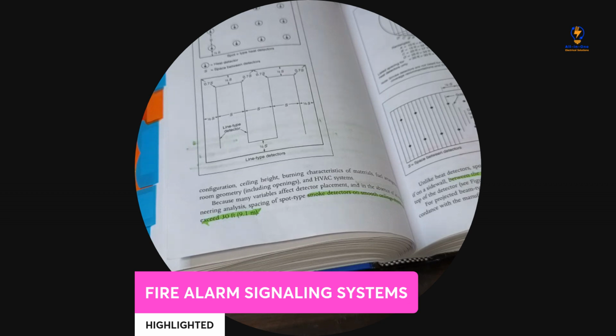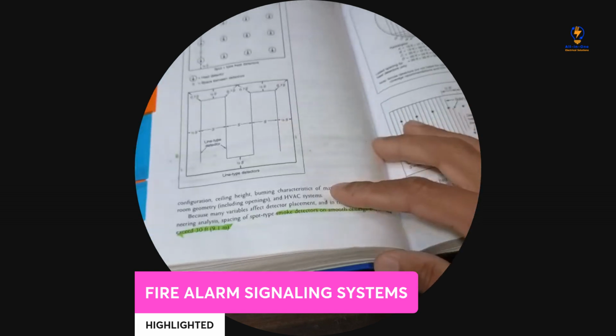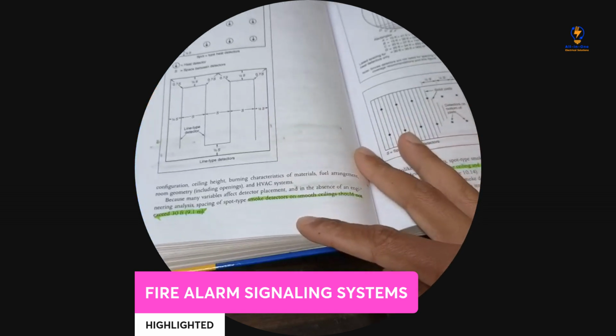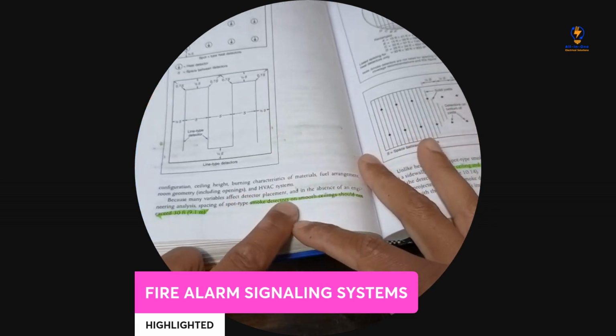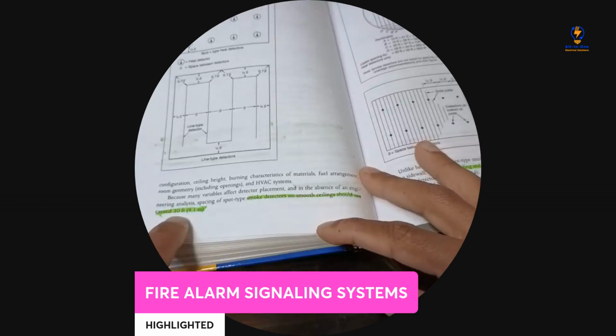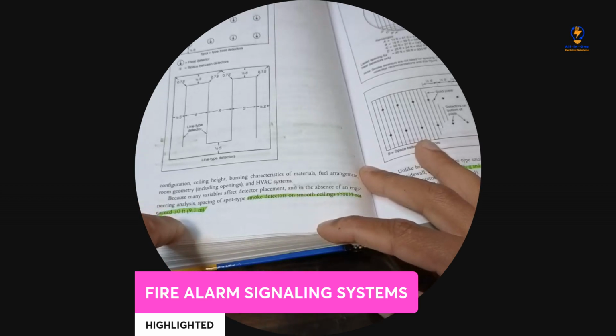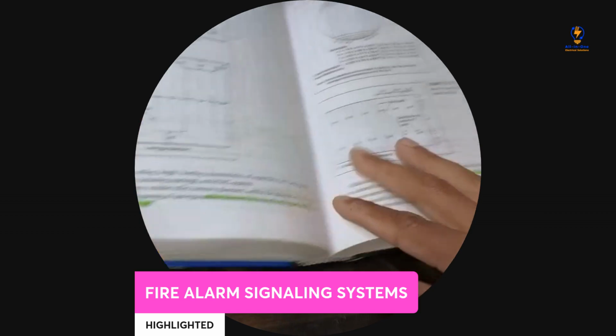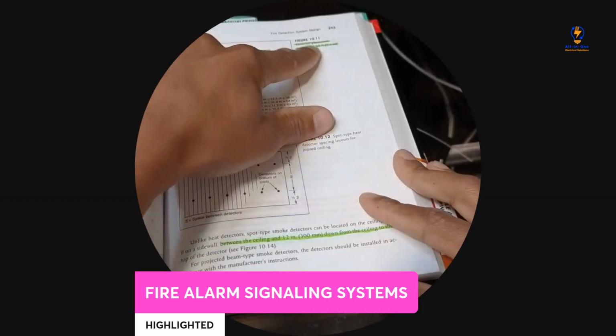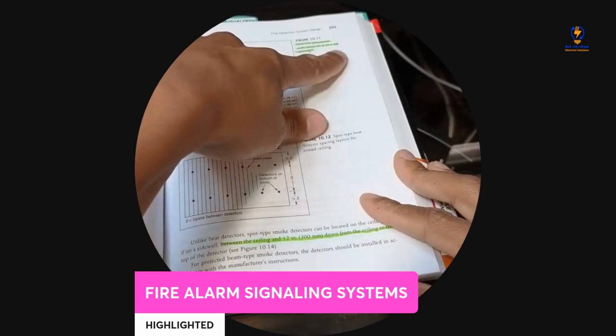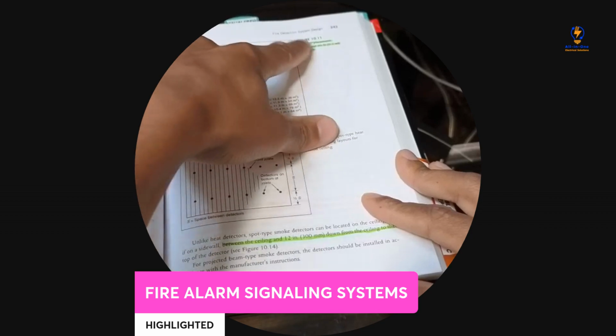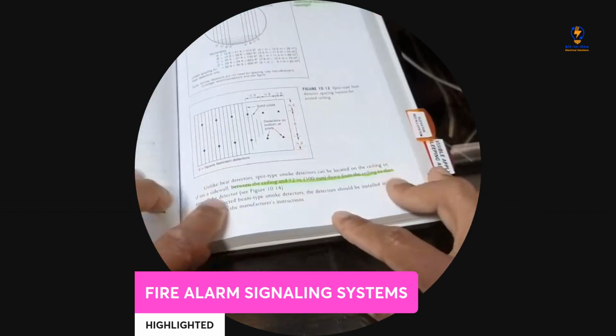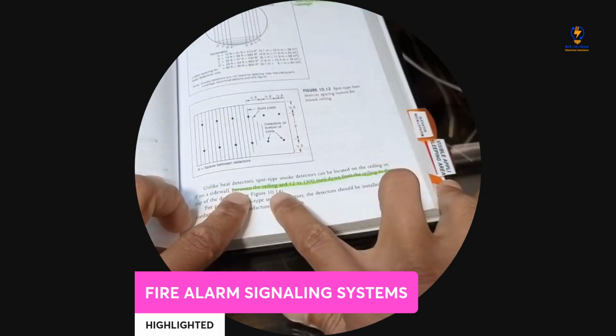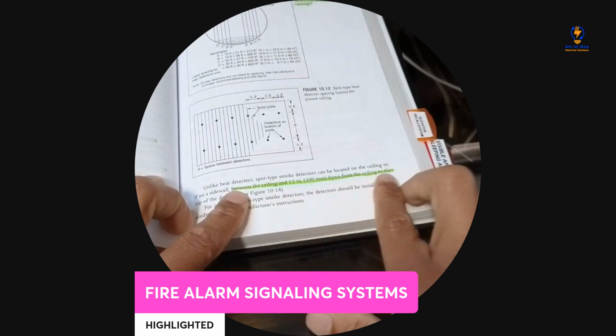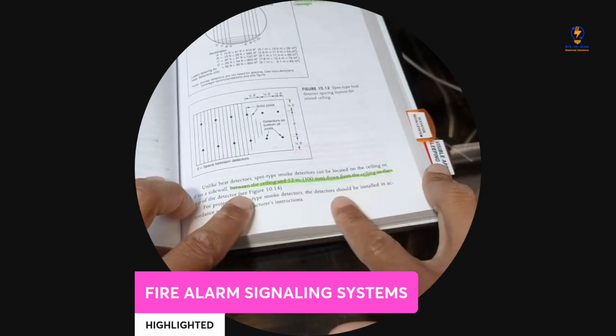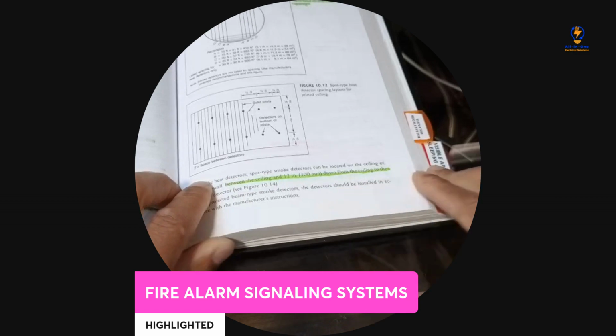And then okay, we're on page 242. Right here, the last two lines. Smoke detectors on smooth ceiling should not exceed 30 feet. Very important, guys. And then on page 243, detector placement which listed 30 feet spacing right here. And then right here, between ceiling 12 inches down from the ceiling to the top of the detector. I highlight this as one, 243.